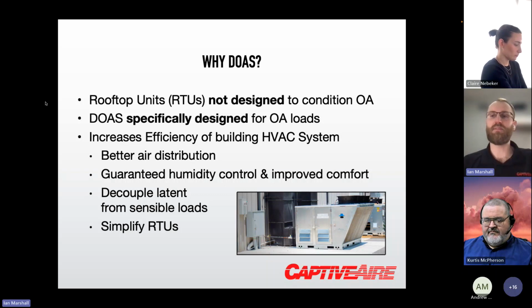So a lot of the times, we'll pair with VRF systems or fan coils, or something along that nature, to essentially have the DOAS be handling the outdoor air distribution for the space, and the other equipment handling the recirc heating cooling needs of the space. Not to say that our DOAS unit can't run as a high outside air or high recirc type unit as well, but that's typically how DOAS is handled because of the humidity loads from the outdoor air. It's a good design approach to separate that with a dedicated unit for the outdoor air loads.